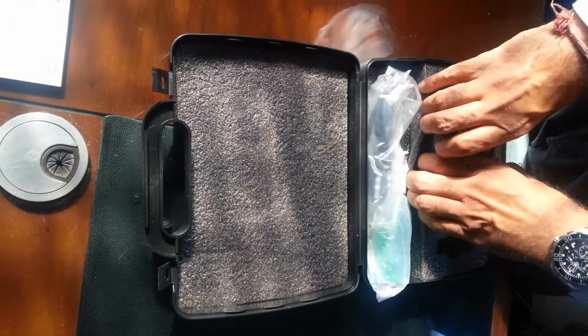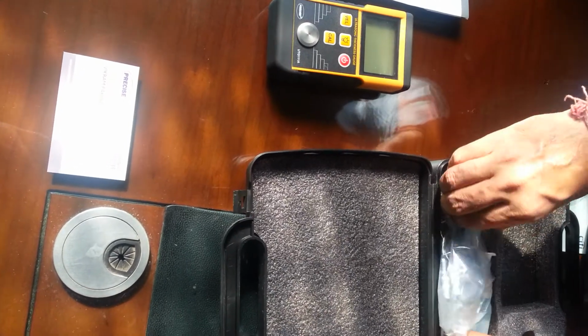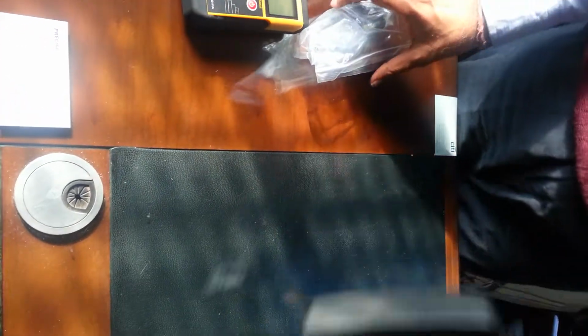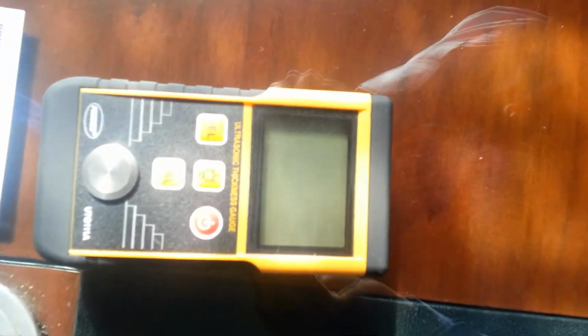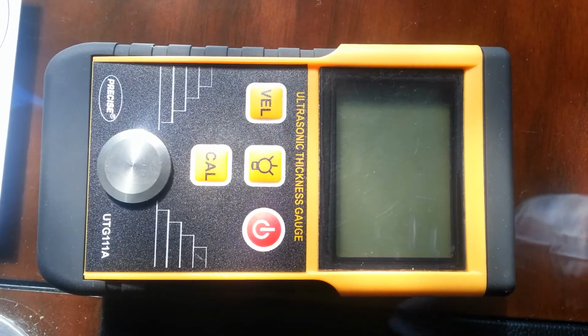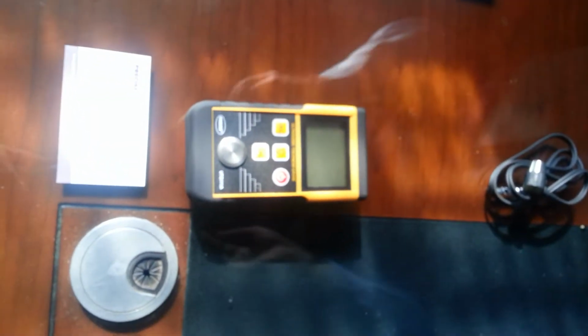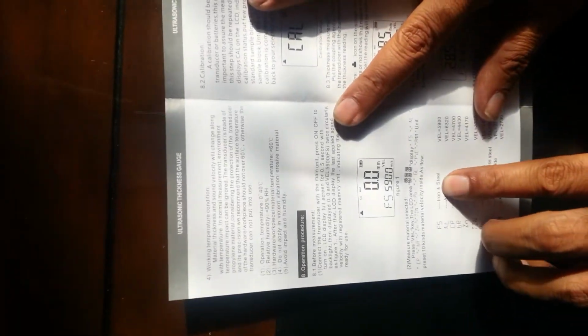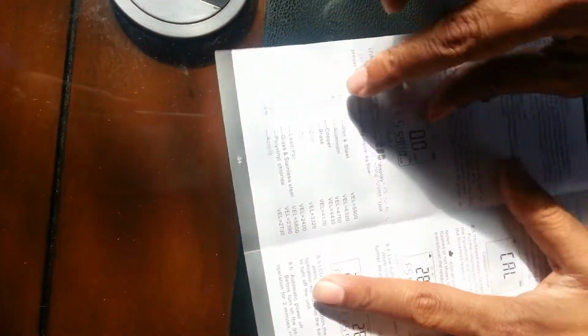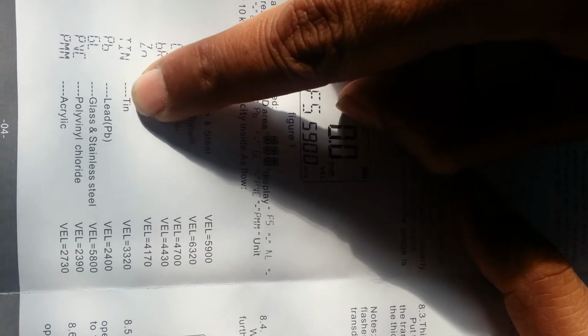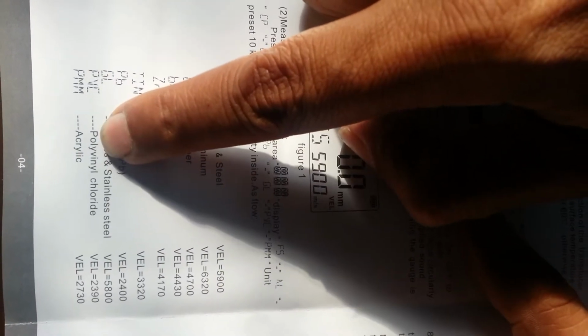Now today we explain to you about a model called UTG 111A. This particular model is a basic model where we can check thickness of maybe 10 components in total. Although it is an ultrasonic thickness gauge, we cannot change the speed of sound in this. It's already built in. So there are particular materials we can check, and in case it's not the standard material, then we need to look for a better model. Here the materials we can check are iron and steel, aluminium, copper, brass, zinc, tin, lead, glass, polyvinyl chloride and acrylic.